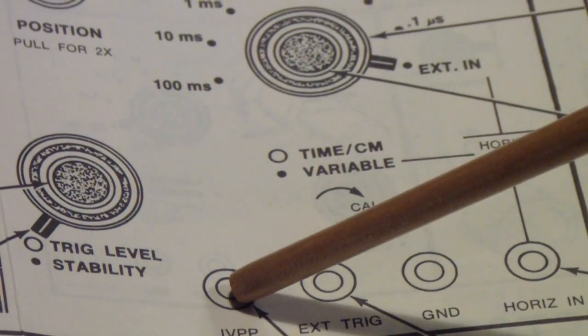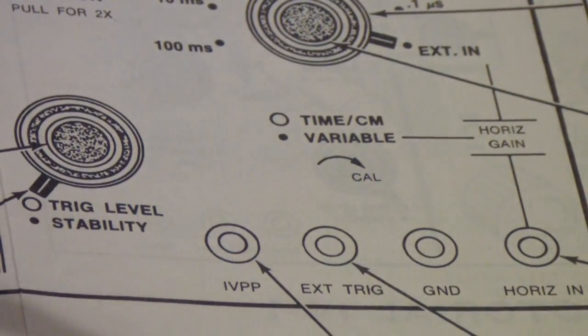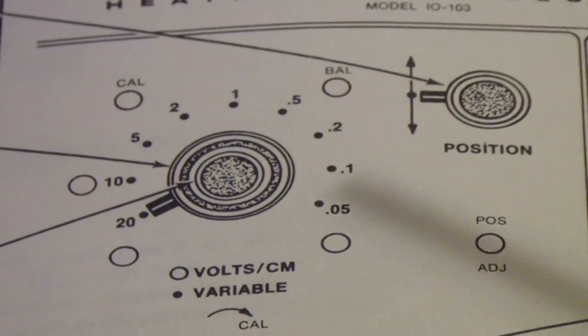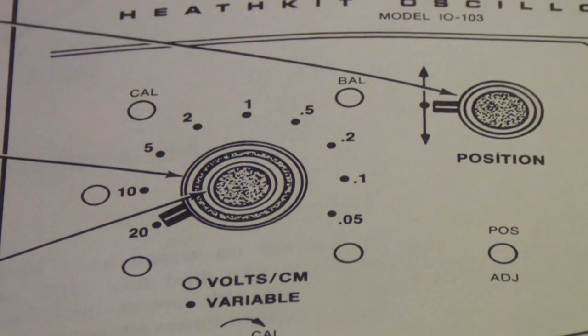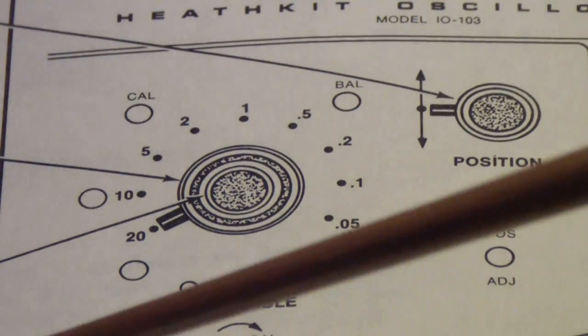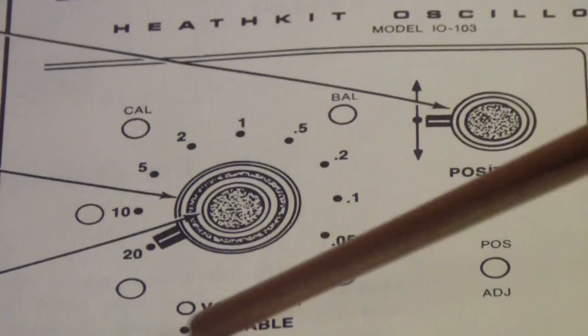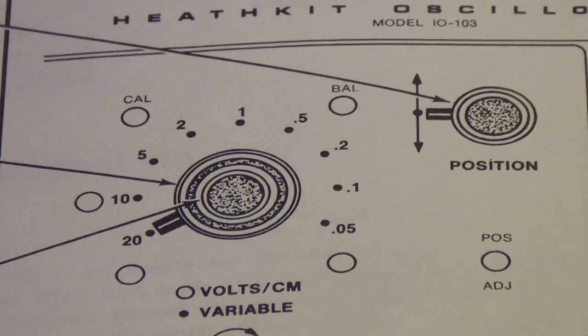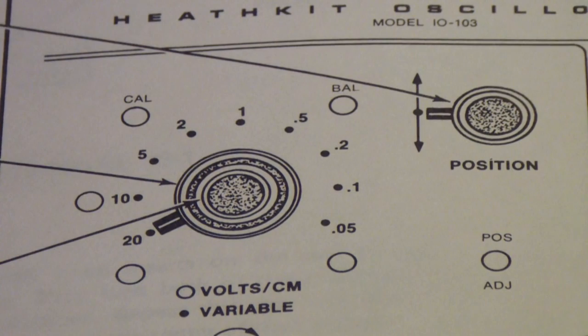You used this 1 volt peak-to-peak as the input signal while you were adjusting the cal and balance. You would apply 1 volt peak-to-peak, adjust the cal. Then you would short the input and adjust the balance, and so on, until you got a balance across the whole range and the calibration within the specifications of the oscilloscope. This was what I was referring to when I said calibrate.